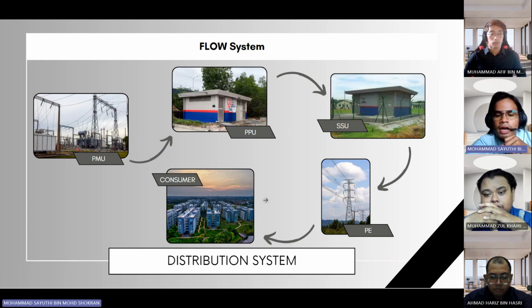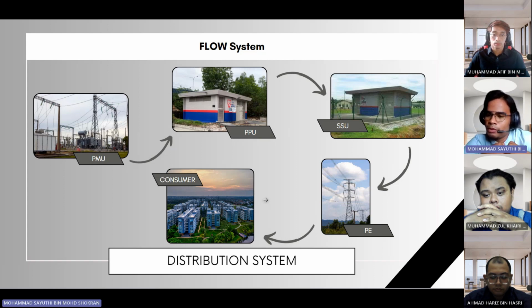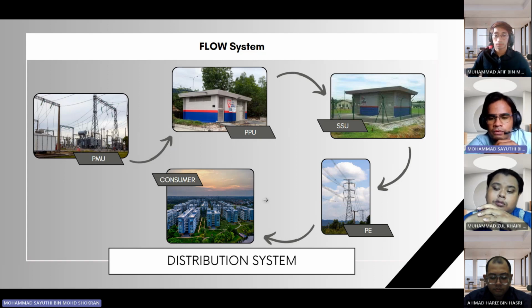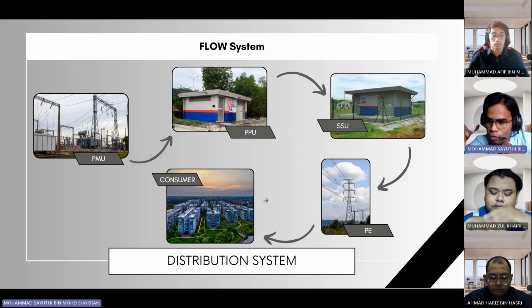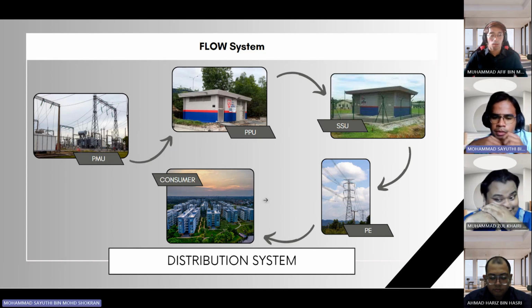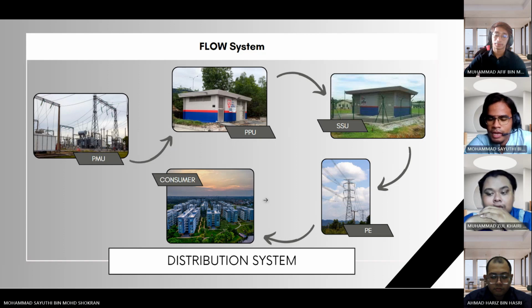Now I want to describe what PMU is and its function. Main incoming substation means pencawang masuk utama. The PMU is a component in the electricity grid whose job is to convert the transmission voltage level either from high to low or low to high for the purpose of energy supply. This PMU accepts the supply from transmission grids, at a voltage of around 275 kilovolt or 132 kilovolt.